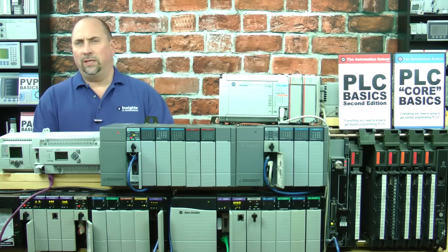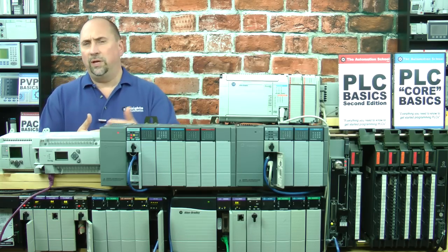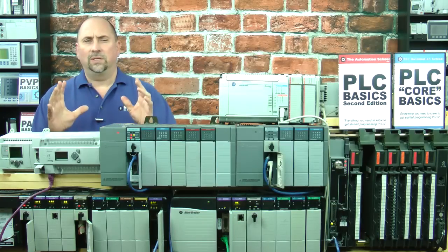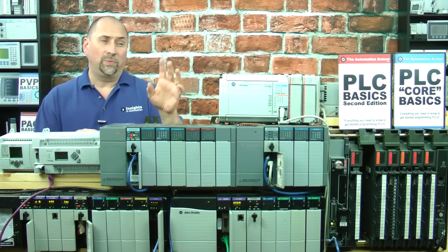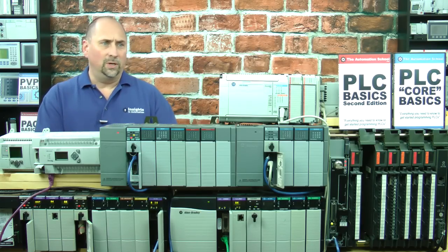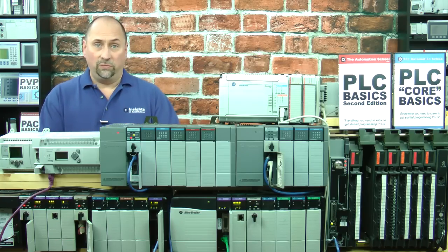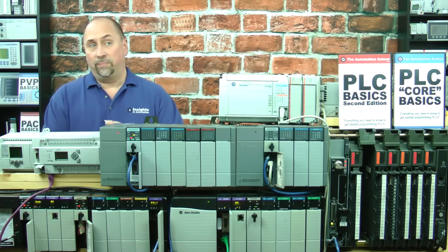Now, to see where that button is, check out our previous video where we did a hardware tour of the actual 1500 hardware, but I just wanted to point that out. If it doesn't connect, try hitting that button and putting it back into default comms. If the port's set up for something else like Modbus or DF1 half duplex or DH485, this isn't going to work. So keep that in mind.